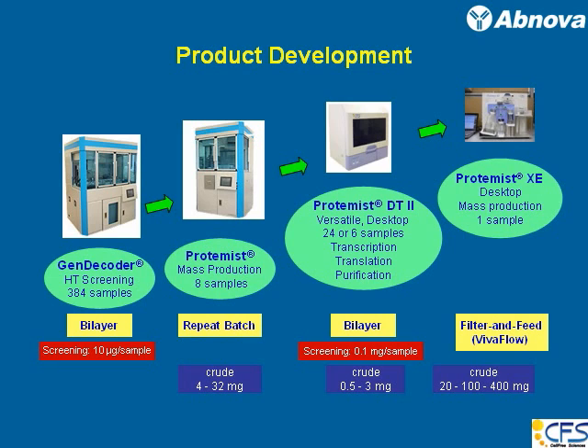That output range puts you in the mid-ground range necessary for either X-ray crystallography or NMR analysis. Rather than keeping all these large robots, we combined two functions together in a smaller unit that is easier to maneuver. This is a versatile desktop protein synthesizer we call the Protemist DT II. It can be operated with either 24 samples or 6 samples, and if you want to express 6 samples, you can do transcription, translation, and purification all in one campaign.